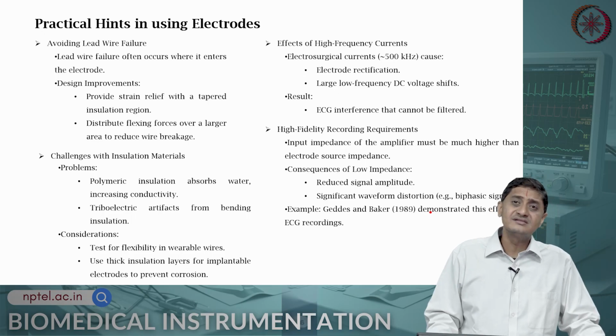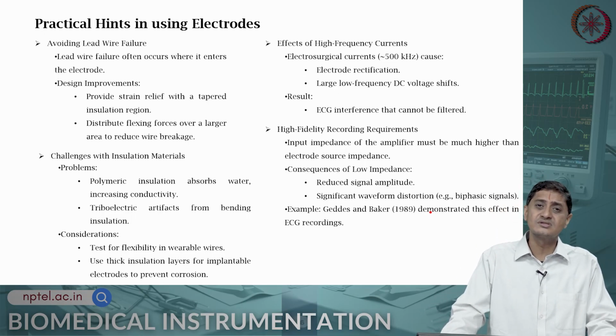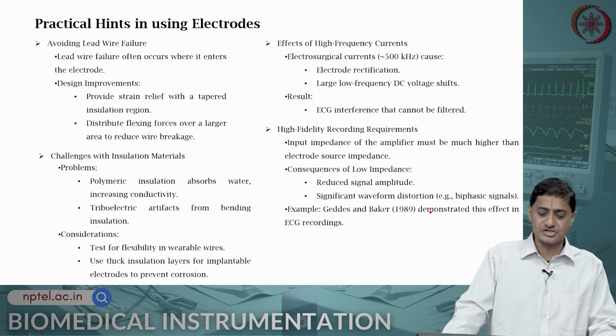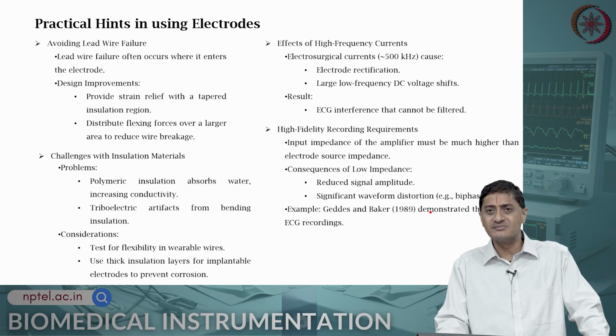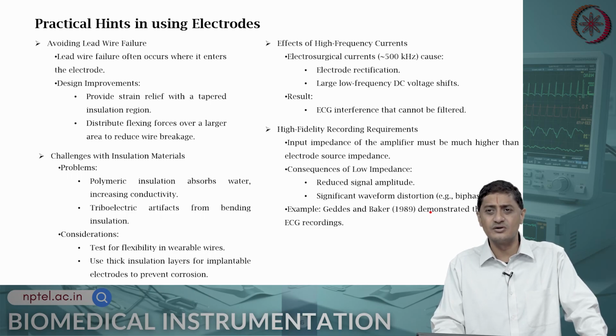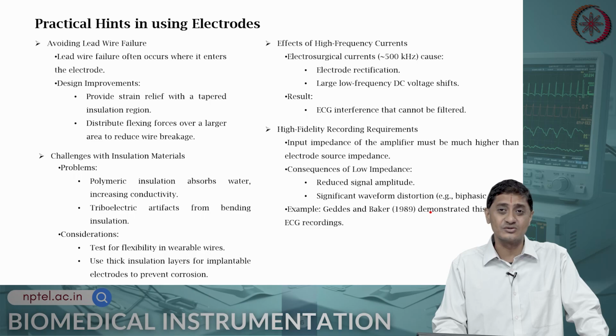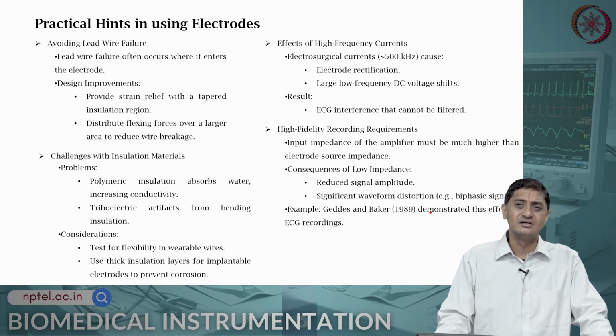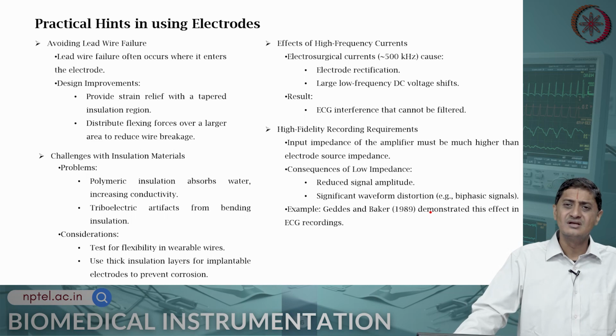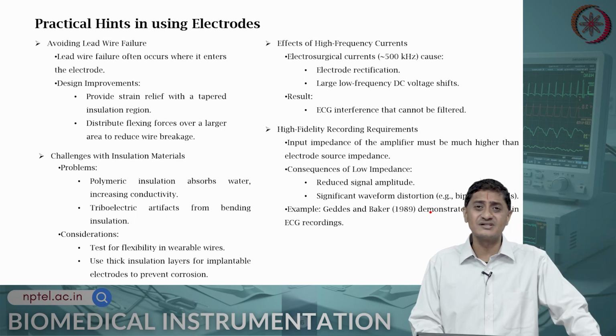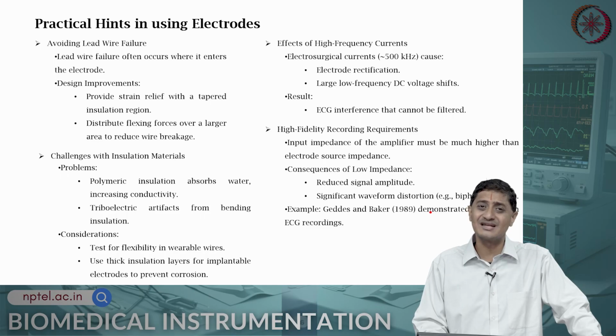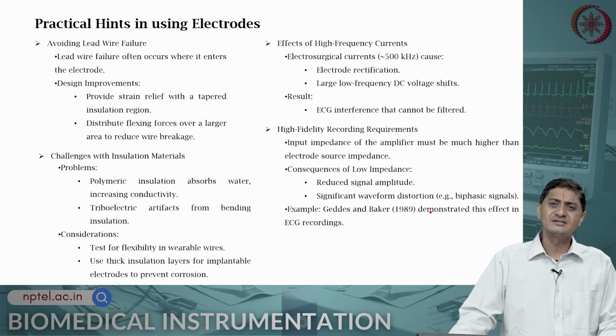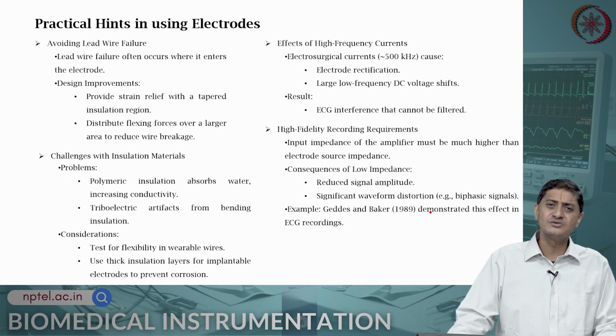The other is the effect of high frequency currents. Suppose you use high frequency currents like in an electrosurgical unit, an electrocauterizer type electrosurgical unit. Sometimes the currents can be of the order of 500 kilohertz. This can cause rectification in the electrode because of large low frequency DC voltage shifts. Also, sometimes ECG interference from other measurements cannot be filtered, and we need to make sure that the recording is done using high fidelity equipment.